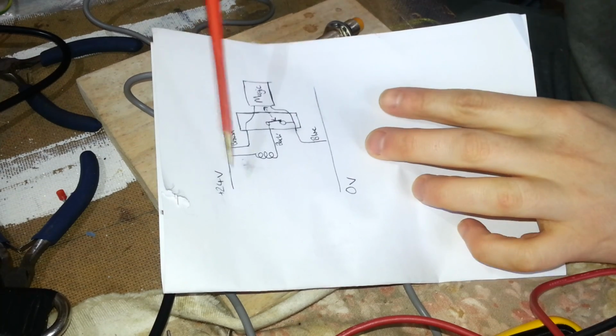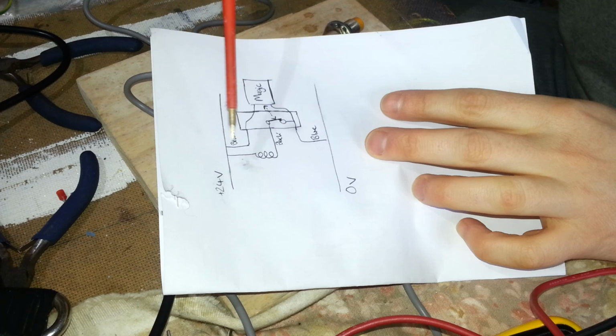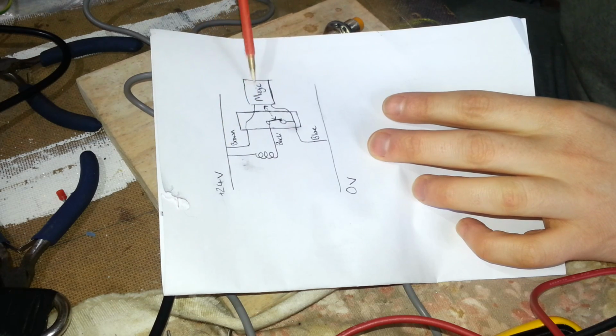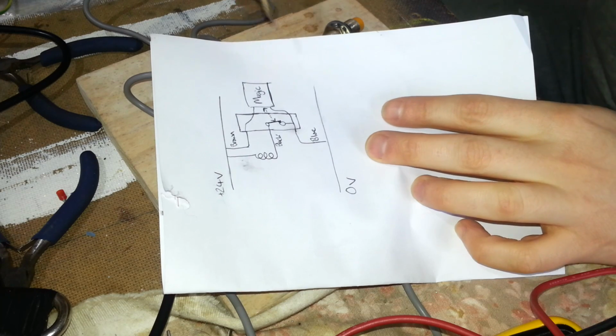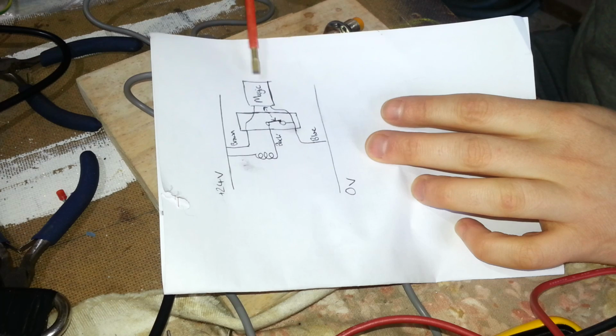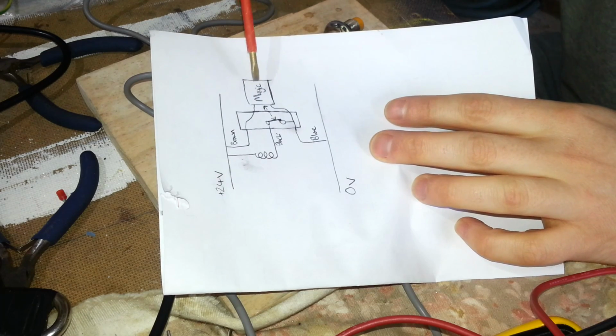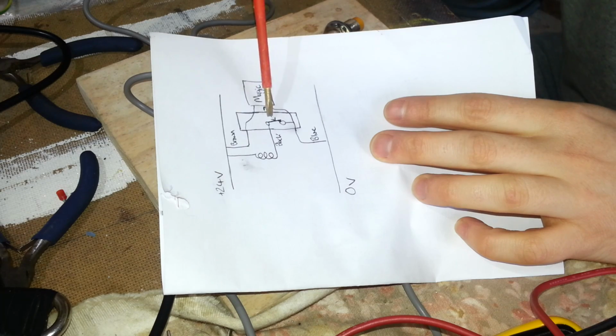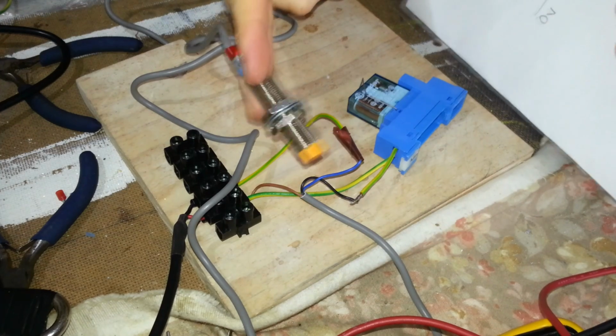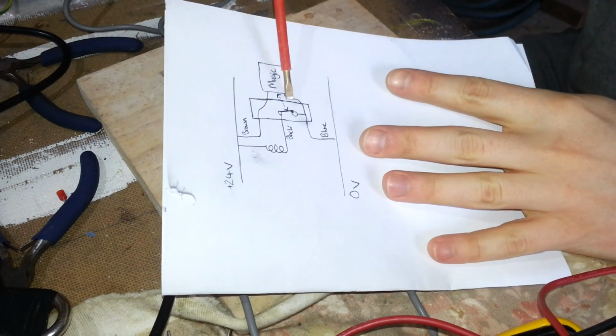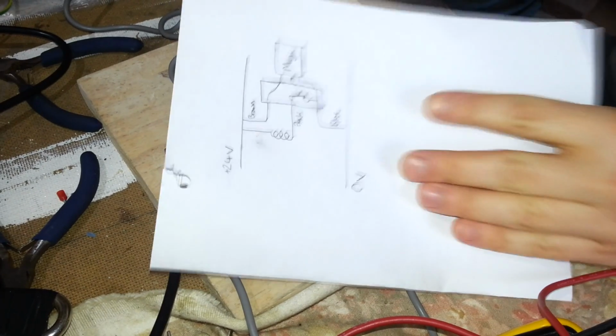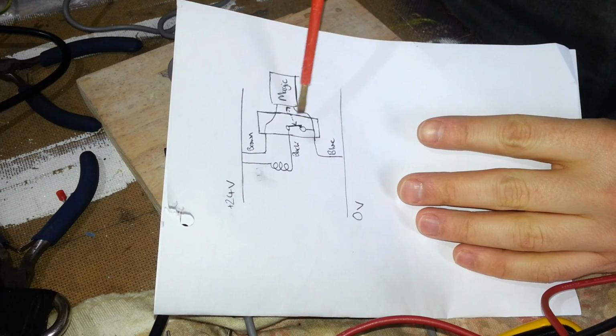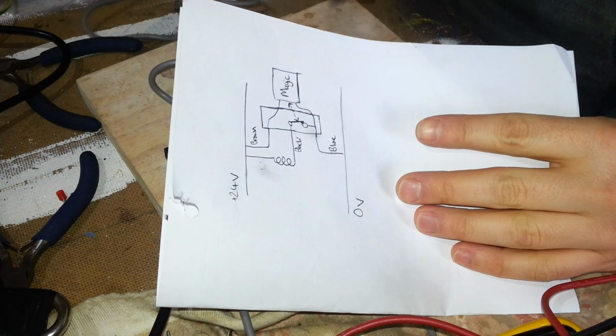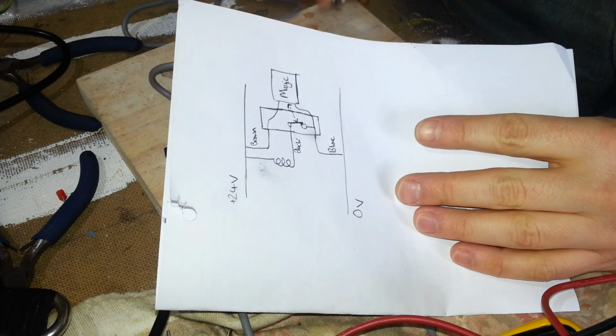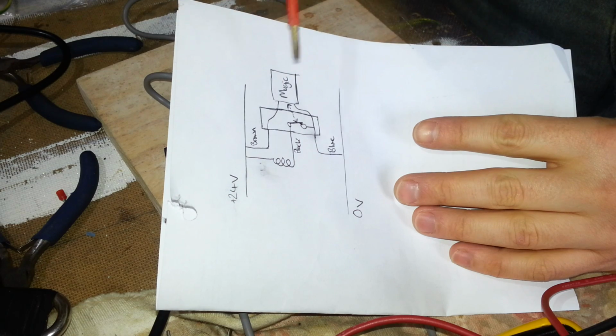So you've got your plus 24 volt rail, or in this test setup, a 19 volt rail. And that powers the magic. And the magic is the bit that senses the metal. So say my screwdriver was coming in here. This magic would sense the screwdriver and then operate this switch. Now, this sensor is normally closed, so it's as drawn on the diagram here, closed. Now, as a piece of metal comes in here, once it gets close enough, within 4 mil, it pulls this switch open.